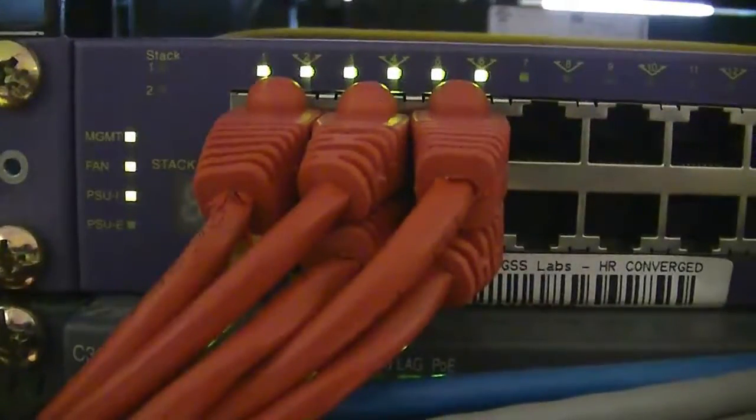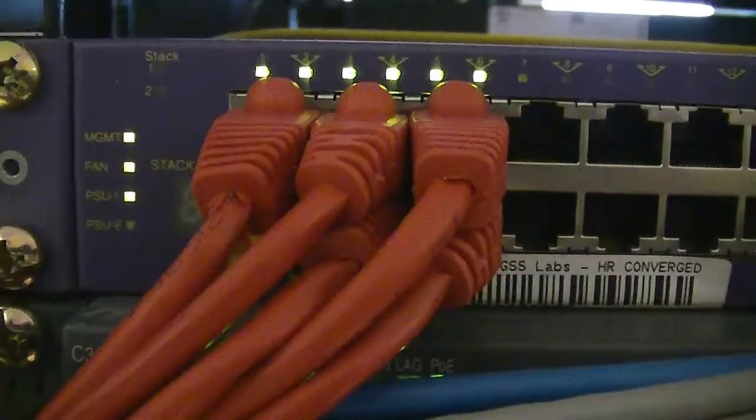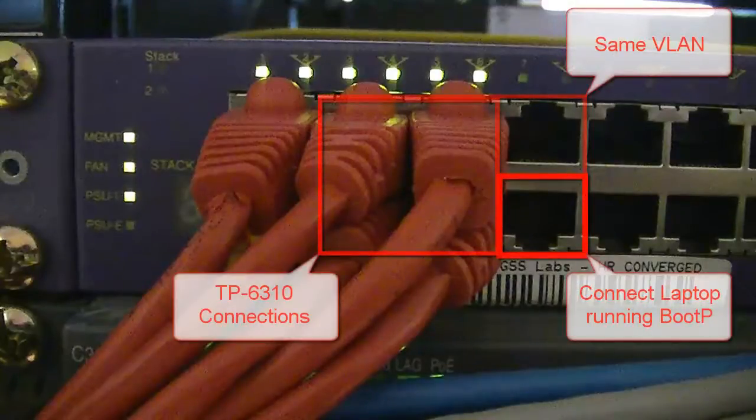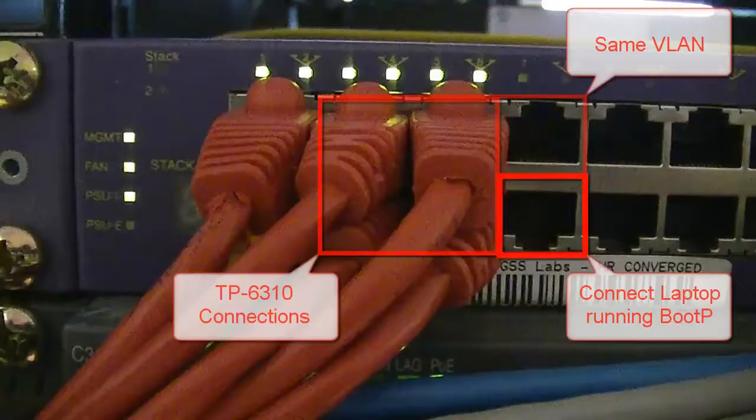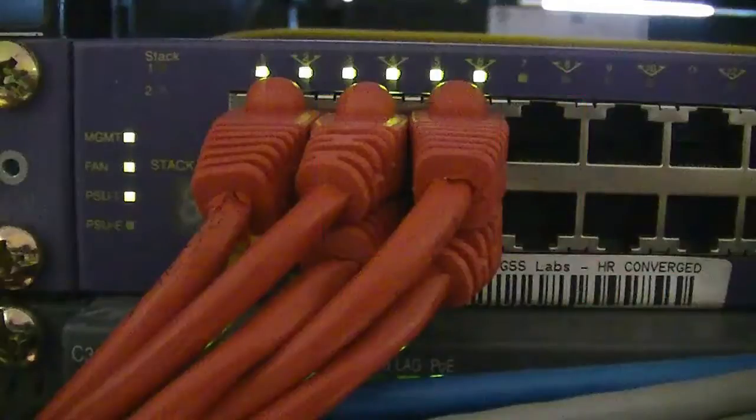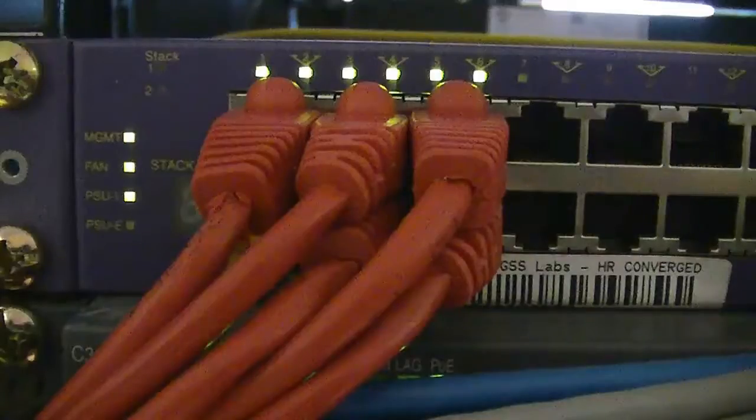The laptop or PC must be connected so it can provide responses to BootP requests sent from the TP boards. If connecting to an Ethernet switch, you will need to make sure that the TP boards and laptop are connected to the same VLAN and that no other BootP or DNS servers can respond to TP board requests. Connected to an Ethernet switch, the BootP server can provide configuration information to both boards sequentially. We will demonstrate an alternate option of separately providing IP address information to the TP boards by connecting a laptop to the TP boards using a crossover cable.